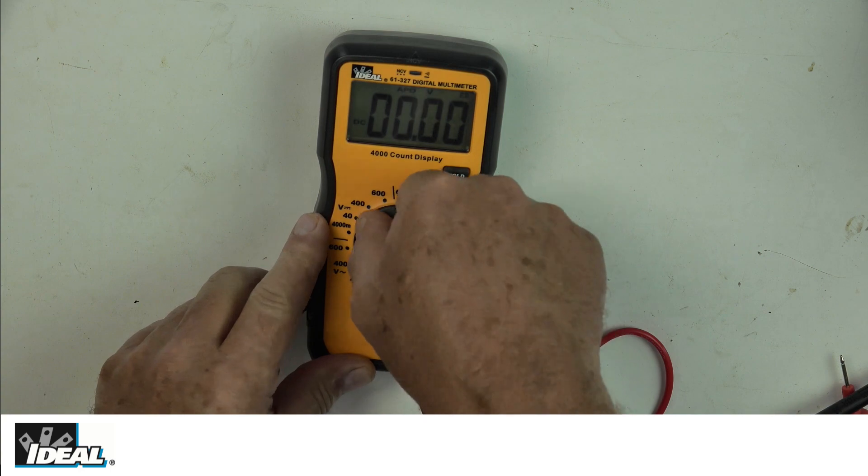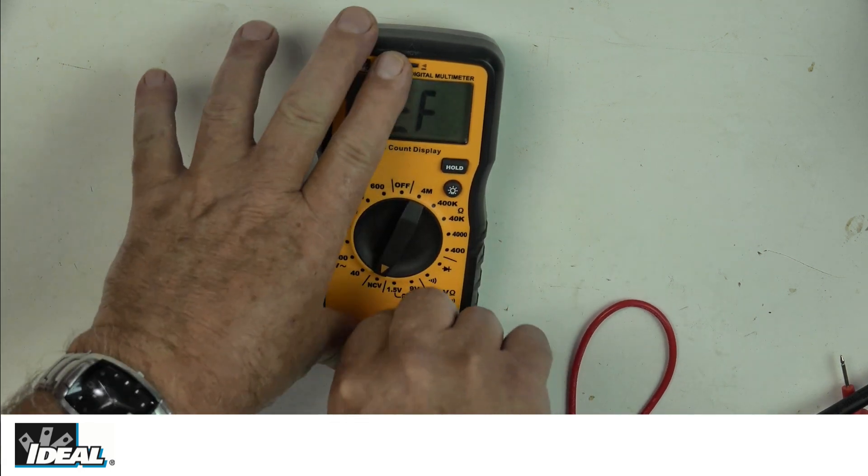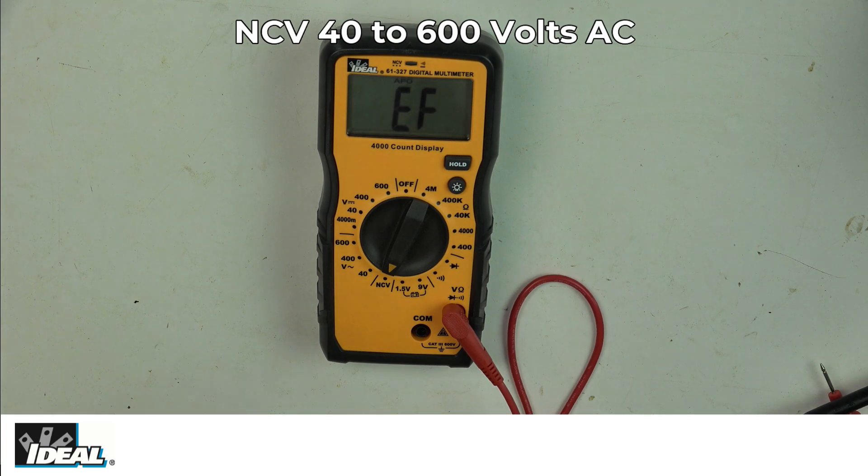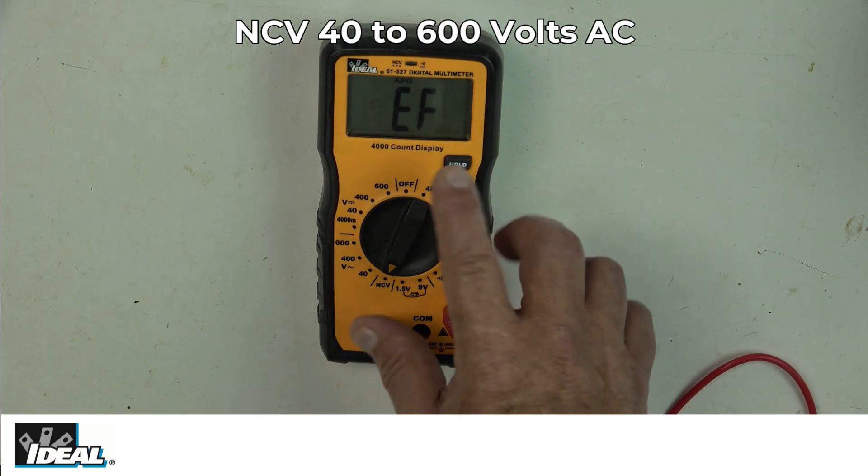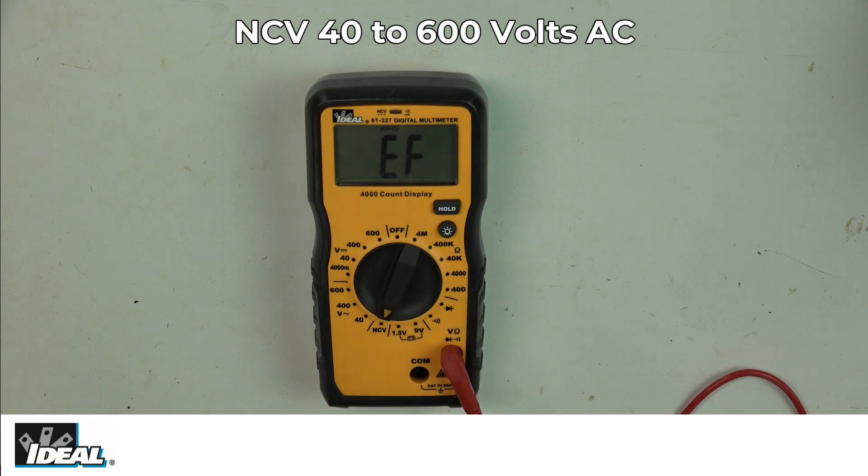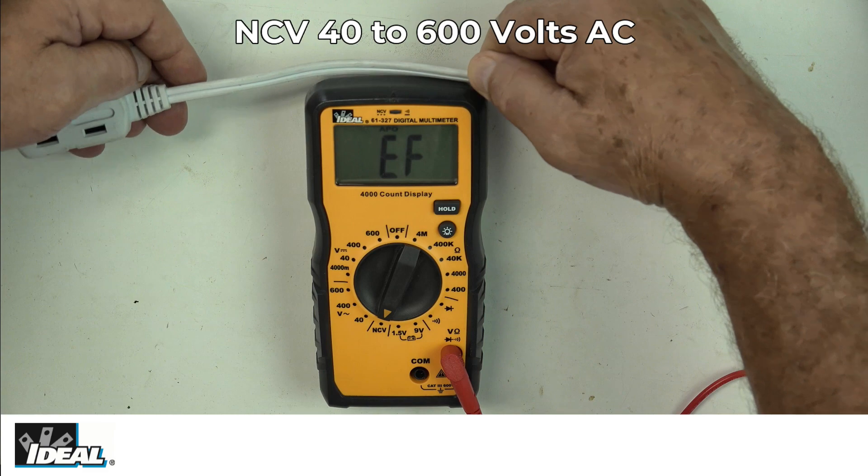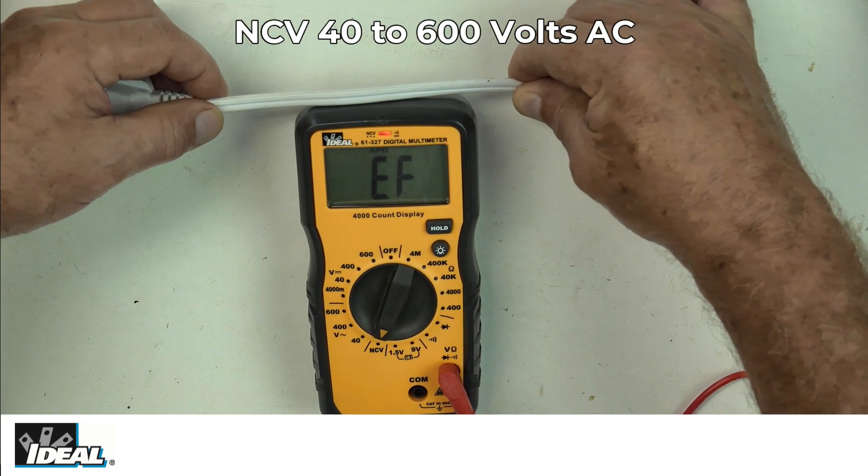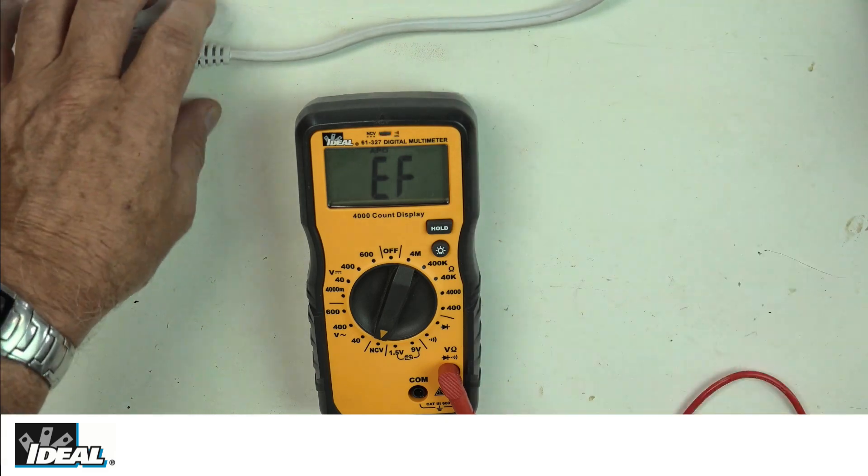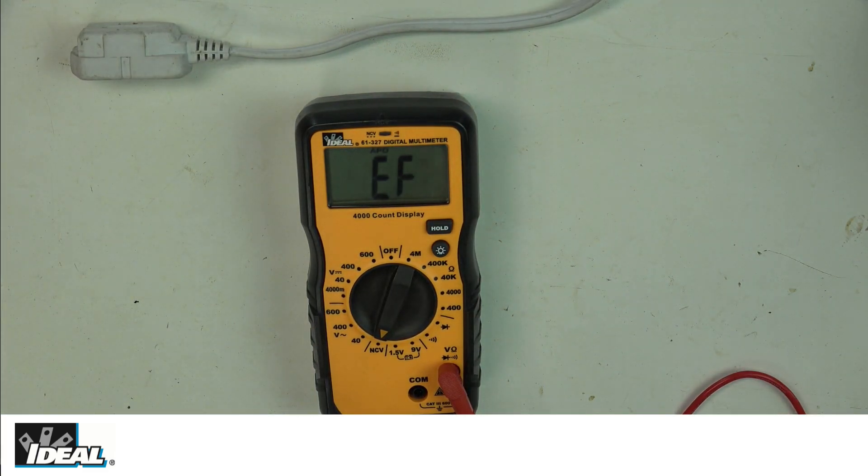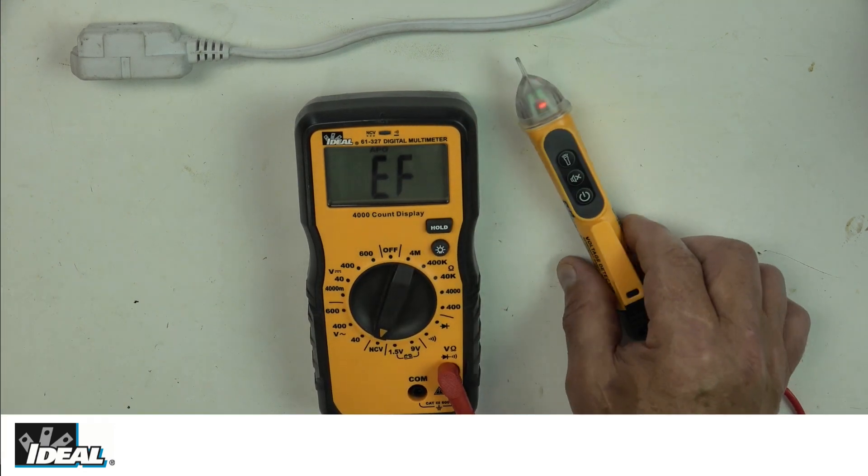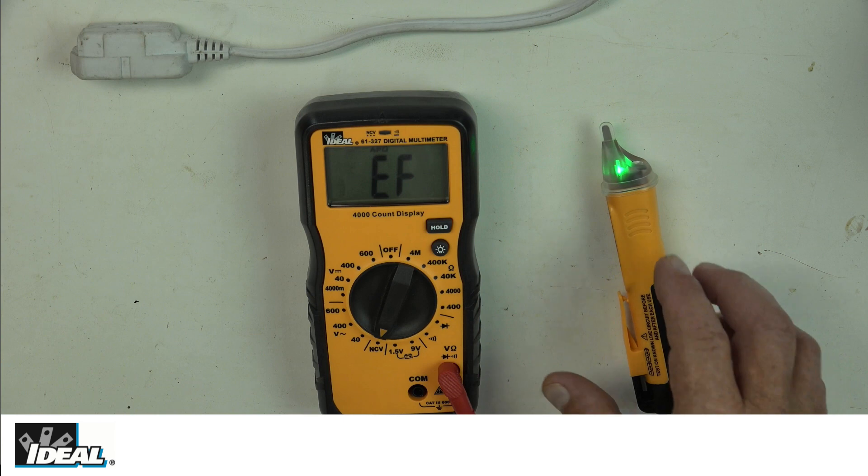The tester also has non-contact voltage sensing capabilities. I'm going to take the black lead out of the tester. You notice the tester says EF on it. If I run a test cord across the back of this tester, it is indicating there is voltage in the cord. But I'm going to tell you that the non-contact voltage sensing capabilities of these kinds of testers versus one of these little voltage sticks is quite a bit different.